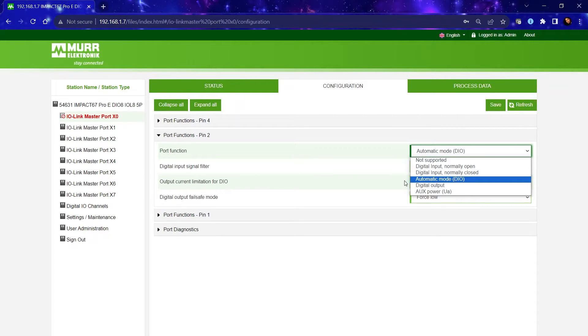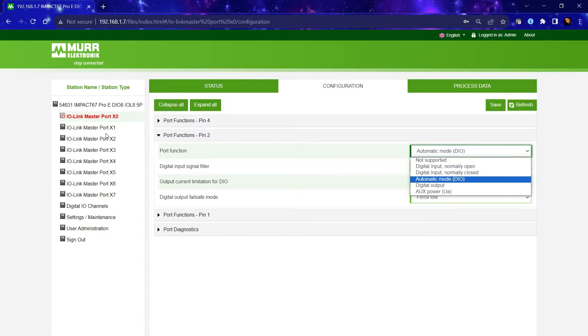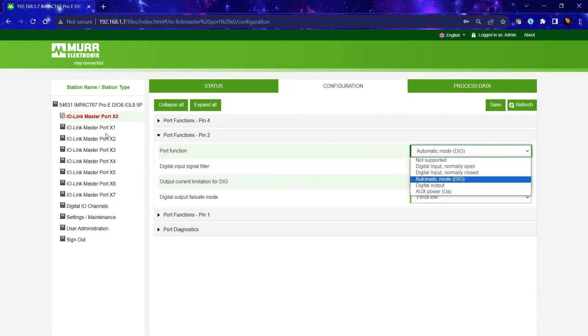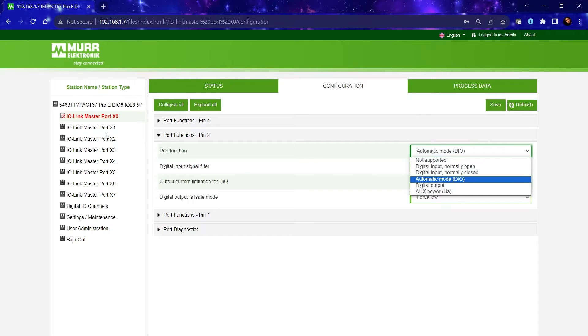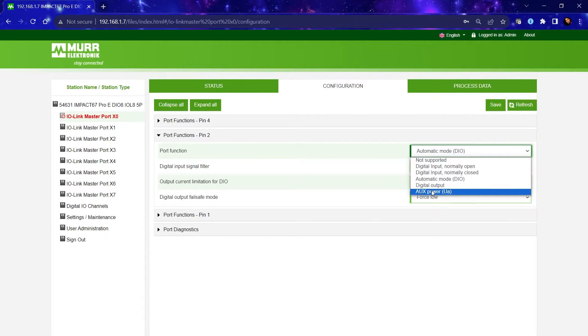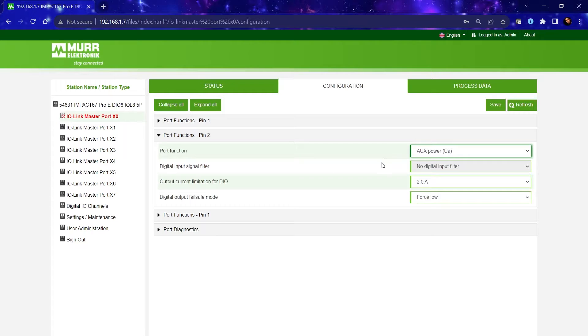you can also configure any of our IO-Link master ports to connect Class A IO-Link devices or Class B IO-Link devices. Now Class B IO-Link devices require a secondary power source. To make that port into a Class B port, you would change the pin 2 function to AUX and it will provide that secondary power source.